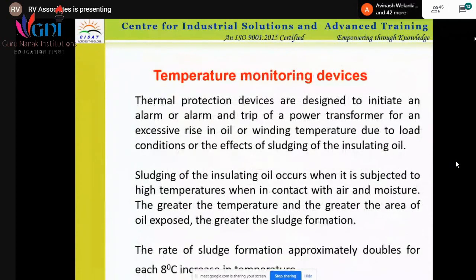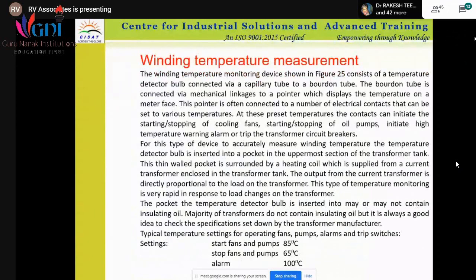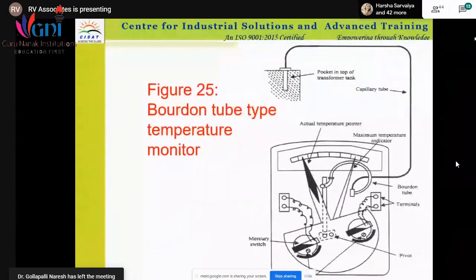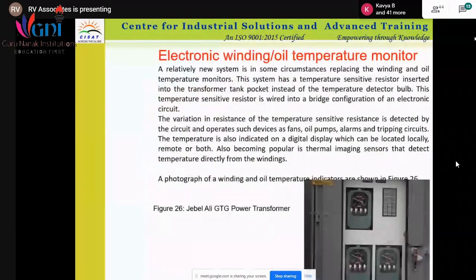Then these monitoring devices are there, like all instruments: WTI, OTI, various sensors. These are all monitoring devices which monitor the present conditions. They are connected to the SCADA, and complete online monitoring is possible with the transformer. All electrical parameters, mechanical parameters, oil parameters, gas parameters are being monitored, and the present system is completely monitored by the SCADA. These are all the instruments which are a support system for the transformer.